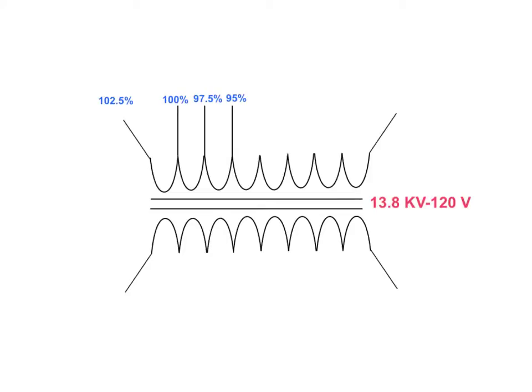This video is going to be a walkthrough of how to handle a multi-winding transformer. When we're dealing with multi-winding transformers, we've got to deal with the turns ratio, and we're going to get that based off of this 13.8 kV to 120 volt rating here.